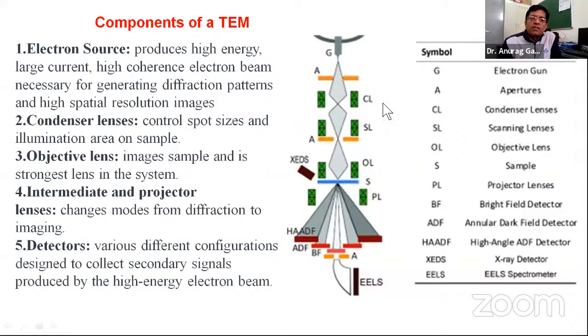With the objective lens, the image of the sample is produced, and then there is the projector lens. With the help of the intermediate and projector lenses, we can switch between diffraction and image formation. So you see that with transmission electron microscopy, we not only get the image of the sample, but we can also get the diffraction. We have to switch the projector lens and intermediate lens, depending on whether we want to get the diffraction pattern or the image. That can be controlled there.